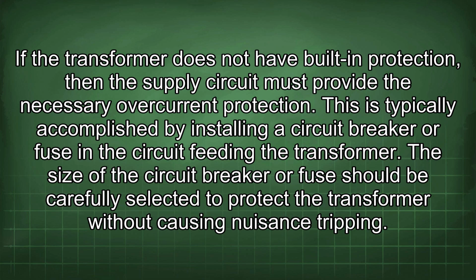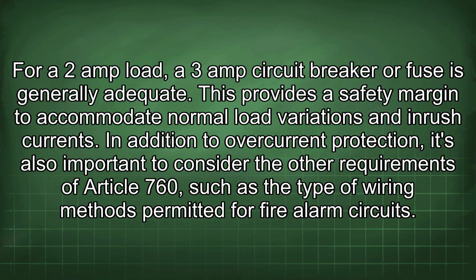This is typically accomplished by installing a circuit breaker or fuse in the circuit feeding the transformer. The size of the circuit breaker or fuse should be carefully selected to protect the transformer without causing nuisance tripping. For a 2 amp load, a 3 amp circuit breaker or fuse is generally adequate. This provides a safety margin to accommodate normal load variations and inrush currents.